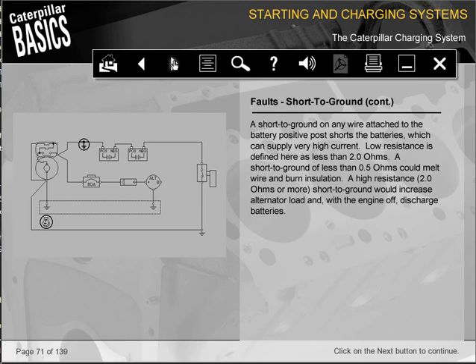A short to ground on any wire attached to the battery positive post shorts the batteries, which can supply very high current. Low resistance is defined here as less than 2.0 ohms. A short to ground of less than 0.5 ohms could melt wire and burn insulation. A high resistance, 2.0 ohms or more, short to ground would increase alternator load and, with the engine off, discharge batteries.